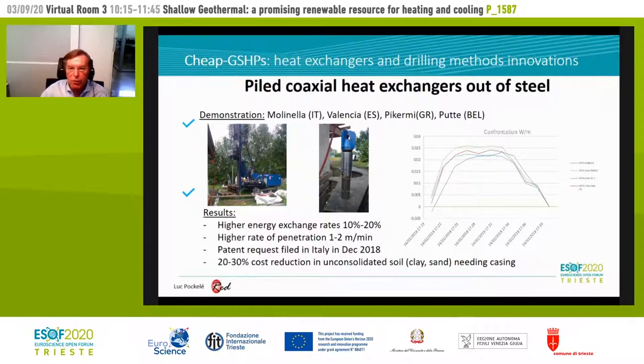You can see on the curve that the reactivity of the coaxial heat exchangers, the green one and the red one, are much higher at the initial beginning of the cycle of the heat pump, and they are pulling much more energy. Heat pumps work on a transitional cycle of 10-20 minutes each time, so the soil has time to reload, rebalance, and retake more energy in the next cycle.